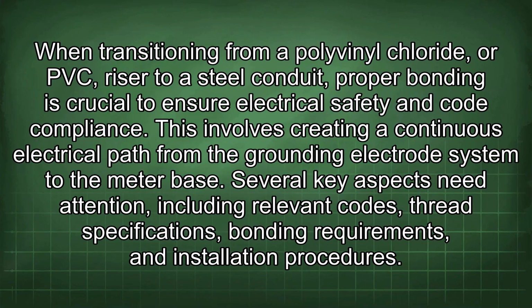When transitioning from a polyvinyl chloride or PVC riser to a steel conduit, proper bonding is crucial to ensure electrical safety and code compliance. This involves creating a continuous electrical path from the grounding electrode system to the meter base. Several key aspects need attention, including relevant codes, thread specifications, bonding requirements, and installation procedures.